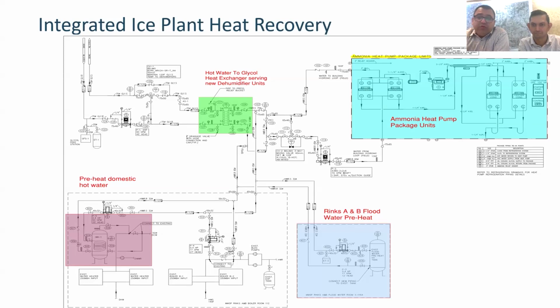So we're in the process of optimizing the system, and the way that we're currently looking at how to extend the run hours and make the system more efficient and extract more heat when it's available, based on the ice plant running hours, is actually reversing and playing with the temperature of the main building heating loop, making it lower than the heat pump, and using the building loop as a heat sink.